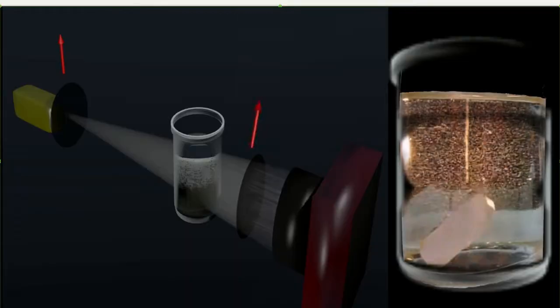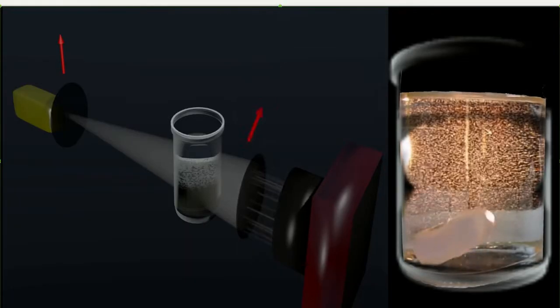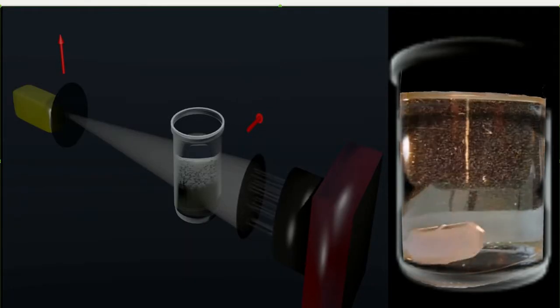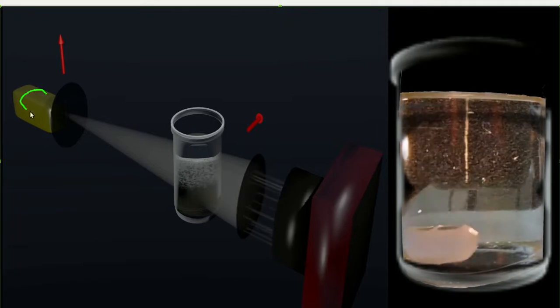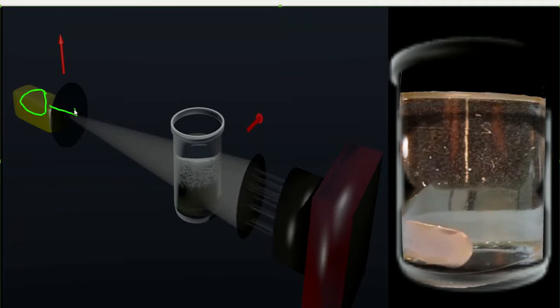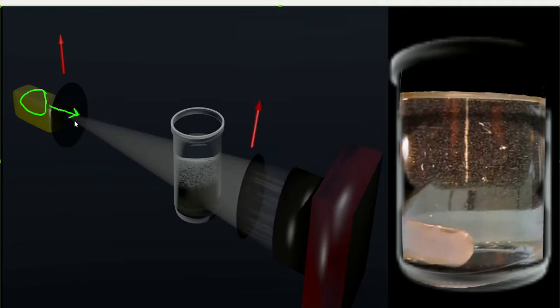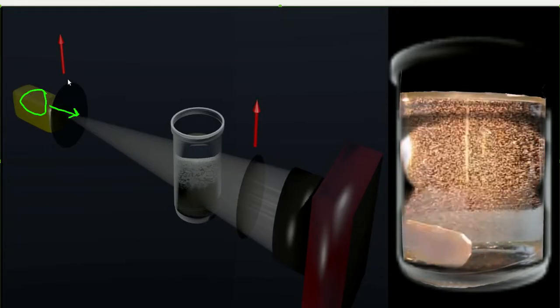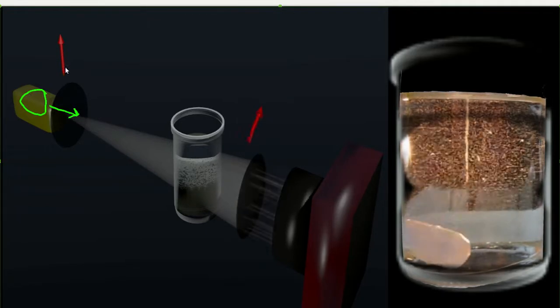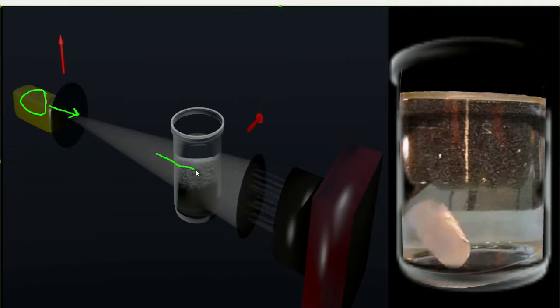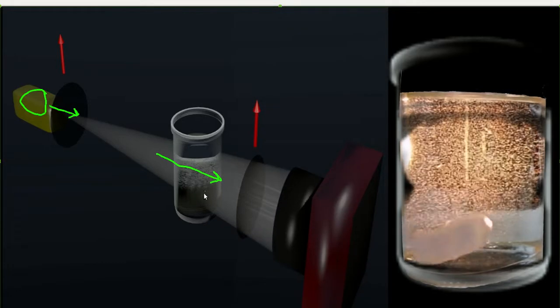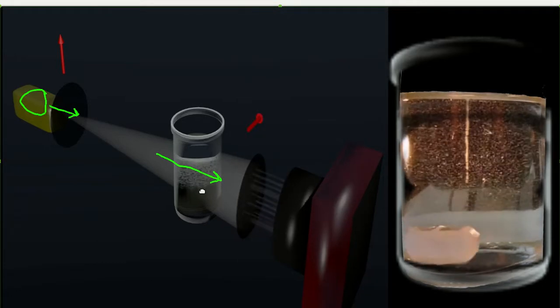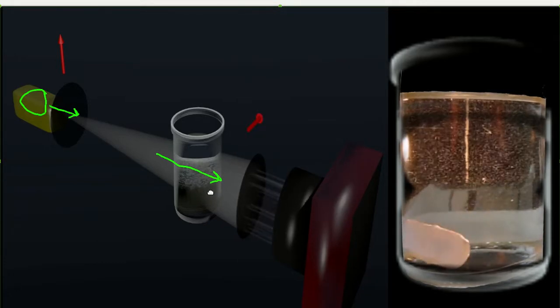To help explain the setup used to measure the API is the following illustration. Similar to the picture, it consists of a light source. The light passes through our first polarizer. The polarization state of the polarizer is indicated by the vertical arrow. The light then goes through our sample in which it interacts with air bubbles, API particles, or anything else in our sample.